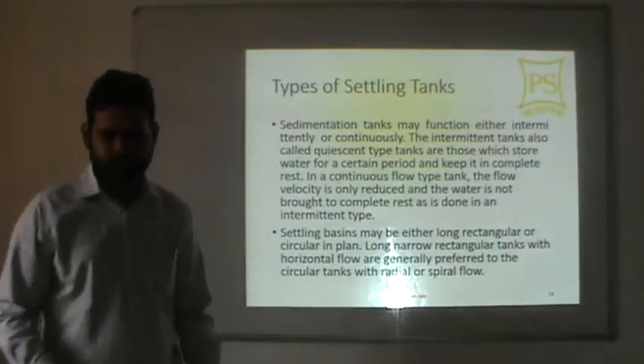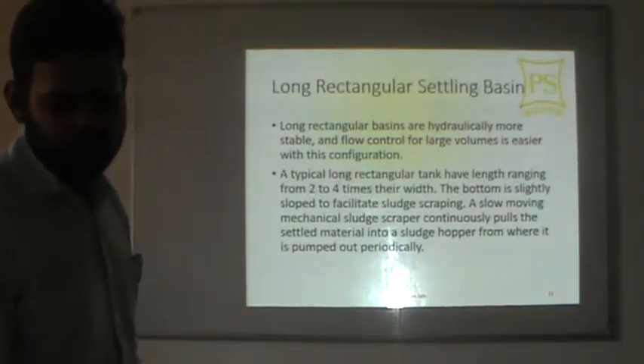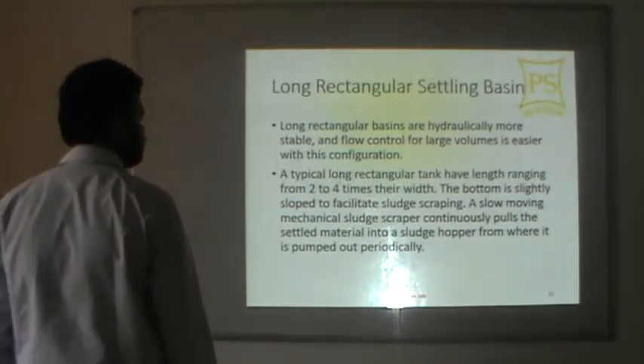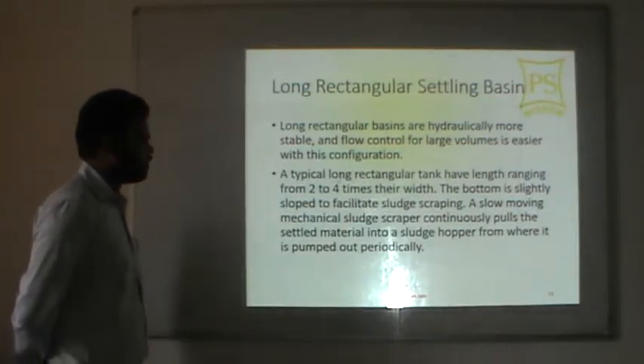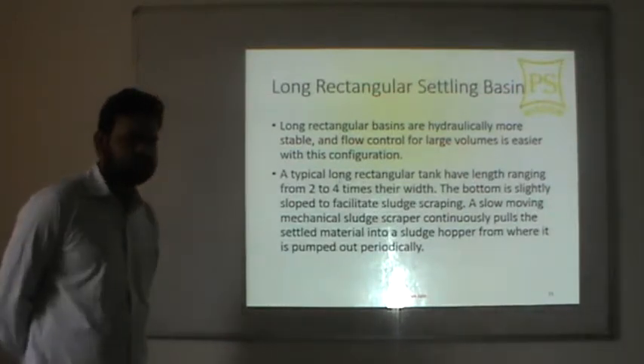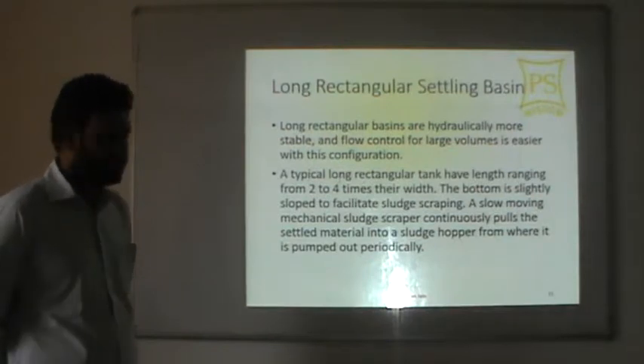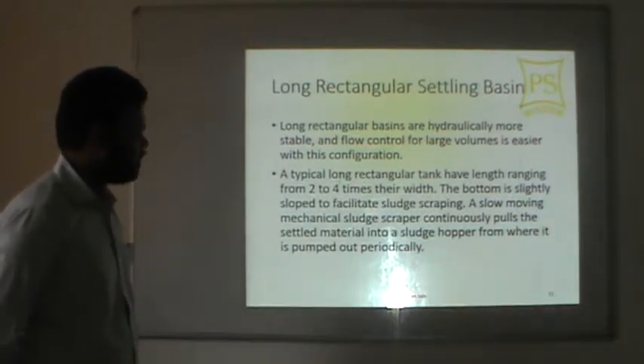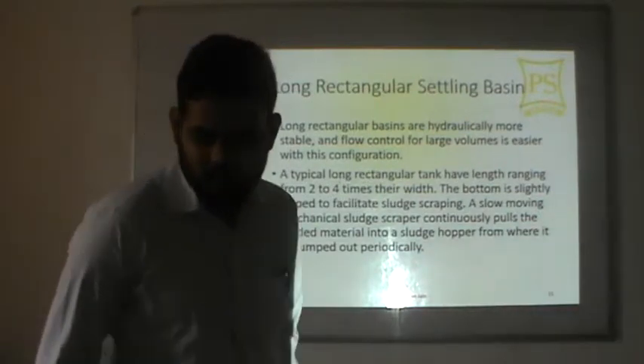In rectangular tanks, flow is horizontal, whereas in radial circular tanks the flow is radial or spiral. Long rectangular basins are hydraulically more stable and flow control for large volumes is easier. A typical long rectangular tank can have a length ranging from two to four times its width. The bottom is slightly sloped to facilitate sludge scraping, and a slow-moving mechanical sludge scraper continuously pulls settled material into a sludge hopper.